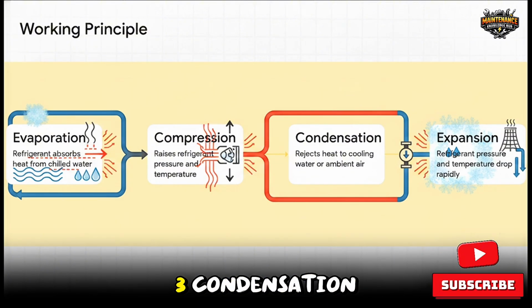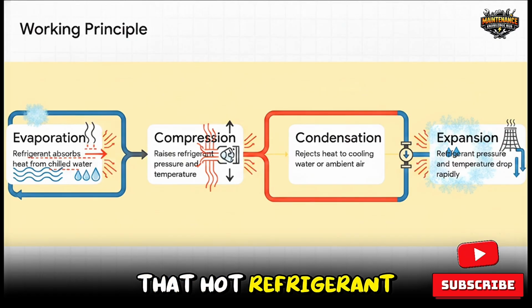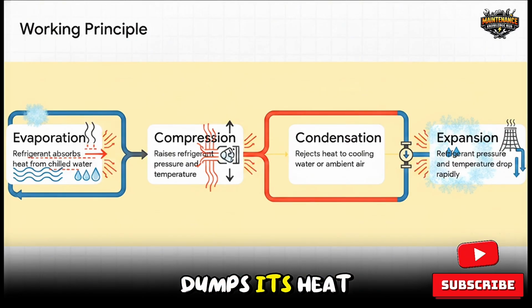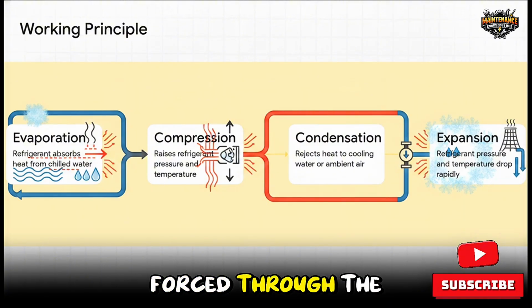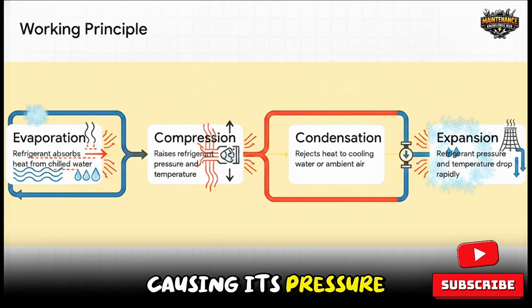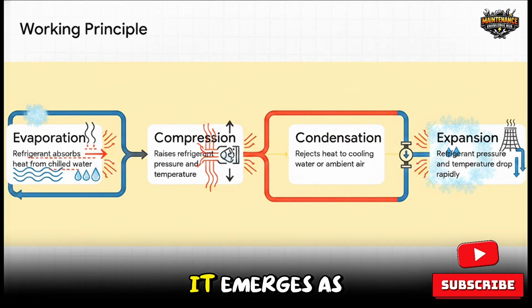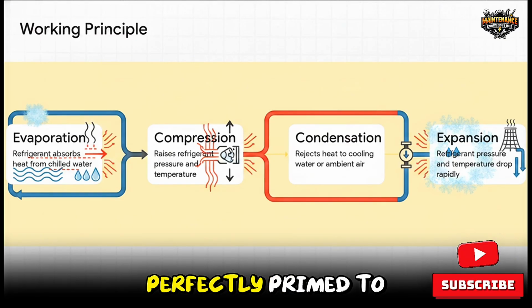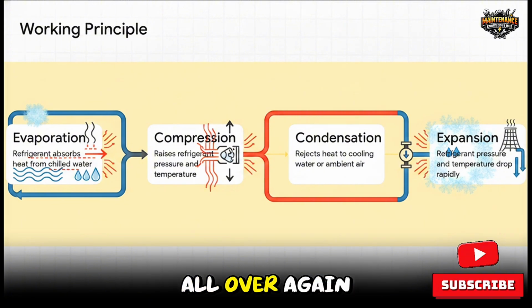Then comes step 3, condensation. That hot refrigerant enters the condenser, dumps its heat into a separate cooling water or air system, and condenses back into a high-pressure liquid. Finally, step 4 is expansion. The liquid is forced through the expansion valve, causing its pressure and temperature to drop rapidly. It emerges as a cold, low-pressure liquid, perfectly primed to steal heat all over again.